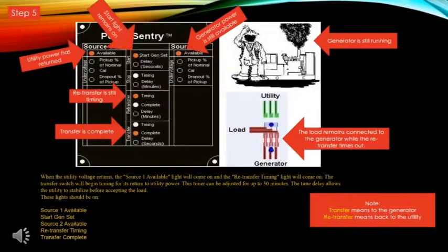Step five: when the utility voltage returns, the source one available light will come on and the retransfer timing light will come on. The transfer switch will begin timing for its return to utility power — this timer can be adjusted for up to 30 minutes. The time delay allows the utility to stabilize before accepting the load. The utility power has returned, the start light remains on, the generator power available is still on, the generator is still running, the load is still connected to the generator, and the retransfer is still timing.